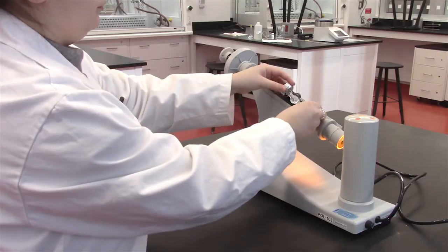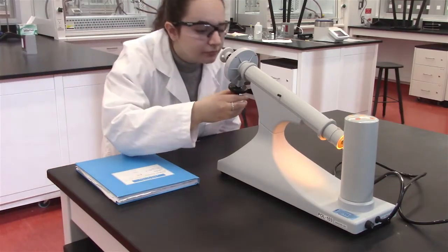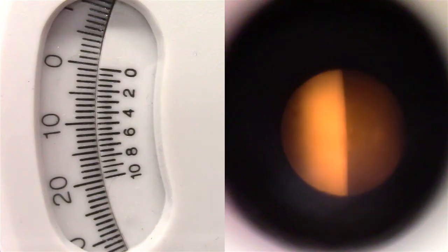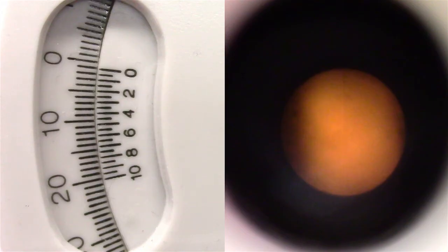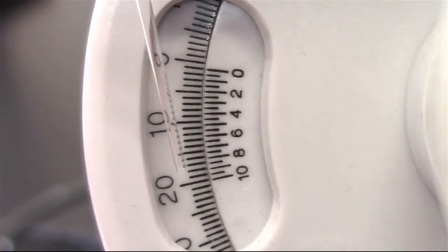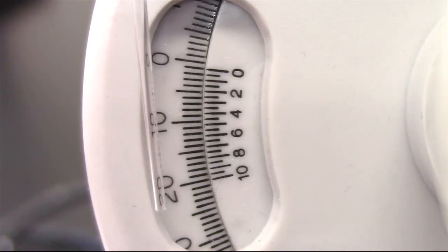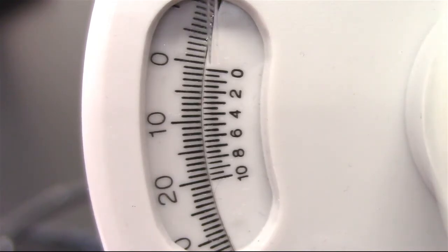Place the sample holder back in the machine and begin to take the reading. You should observe a half-dark circle on the left and a half-dark circle on the right when you rotate the dial in opposite directions. Adjust the dial so that one full circle is seen. Now you can read the observed degree of rotation using the numbers on the outer dials. The outer scale is the whole number for the observed rotation reading and the inner scale is the decimal point for the observed rotation reading.